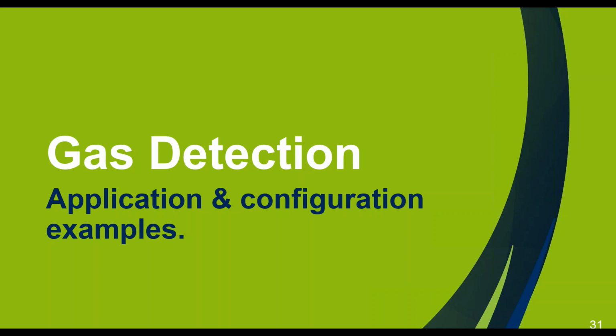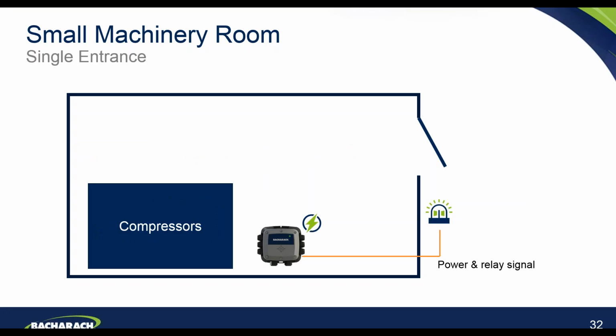So, just as an example, we have a small machinery room here. You have the MGS-450 detector with a power supply in that machinery room. The detector is providing an audible and visual alarm inside the room, so it's meeting the requirements, therefore, of the necessary standards. And then from that detector, it's driving power through the relay to an outside beacon and sounder, which is outside the entrance. So again, very simple, easy example of how the detector can be used to support compliance with the regulations.